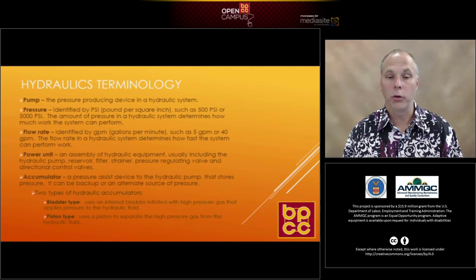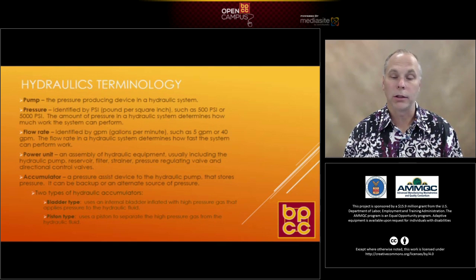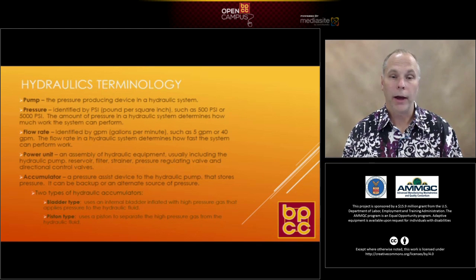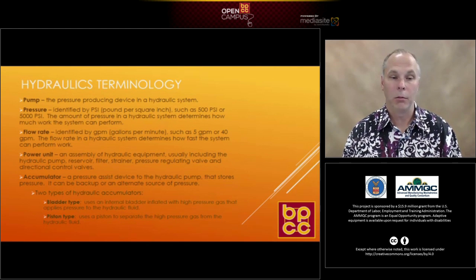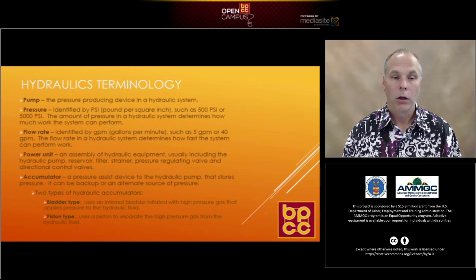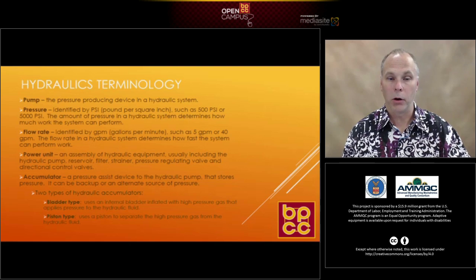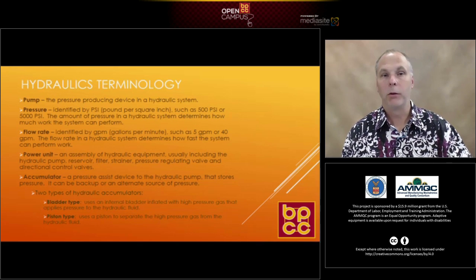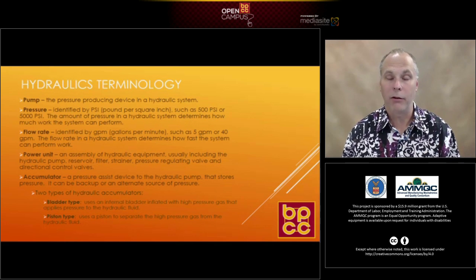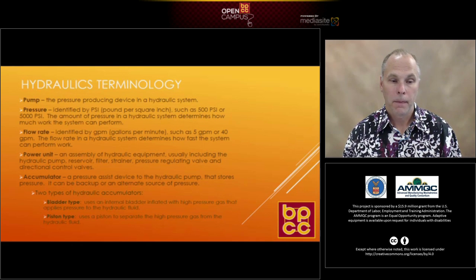The amount of pressure in a hydraulic system determines how much work the system can perform. If you have a 500 PSI system, everything in that system must be rated for 500 pounds or greater. You wouldn't want tubing connected to a cylinder or a hydraulic pump rated at only 50 PSI when the system is actually 500 PSI — you're creating a very unsafe condition.